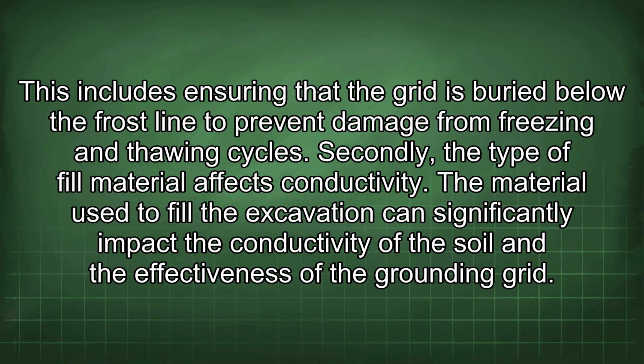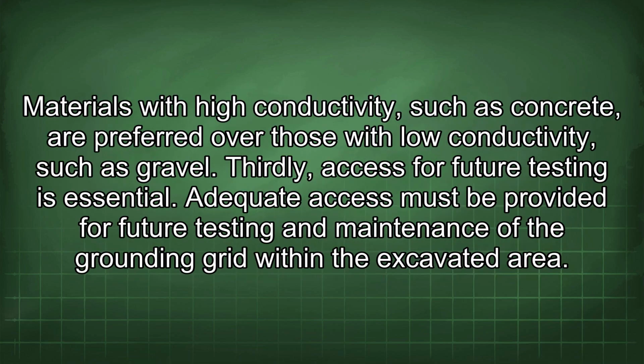Secondly, the type of fill material affects conductivity. The material used to fill the excavation can significantly impact the conductivity of the soil and the effectiveness of the grounding grid. Materials with high conductivity, such as concrete, are preferred over those with low conductivity, such as gravel.